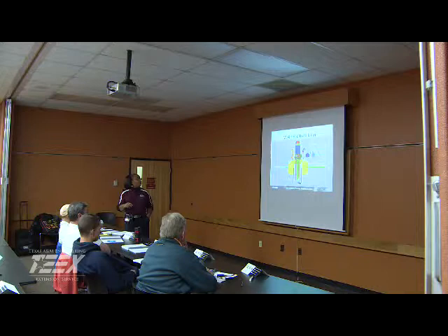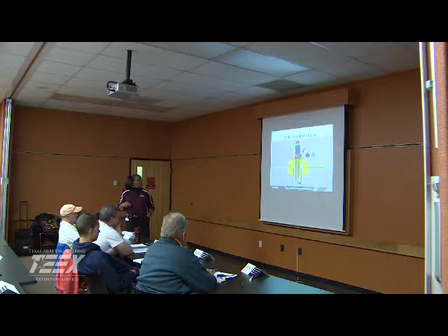All right, so again, what is this right here? This is our well picture here. We have our concrete sealing block that extends 18 inches above the floor of natural elevation. Again, properly sloped concrete. We have the casing. We have the pressure cement on that casing. The air vent there. We have the sampling cock, air relief valve, and we have a check valve.